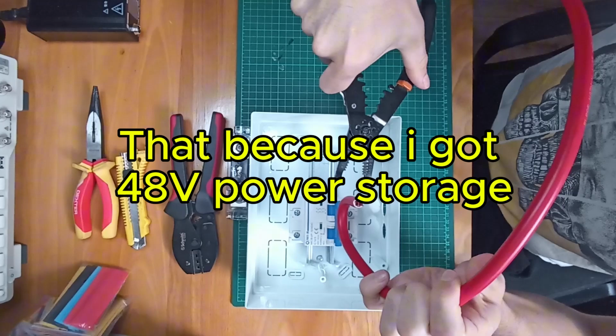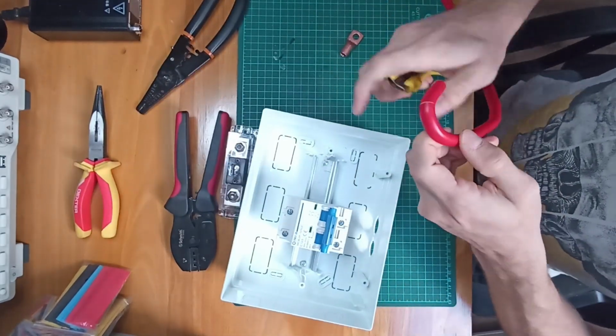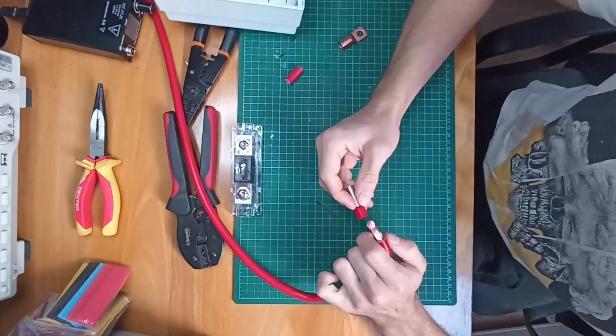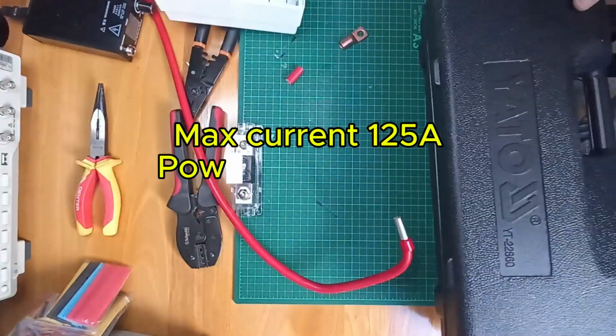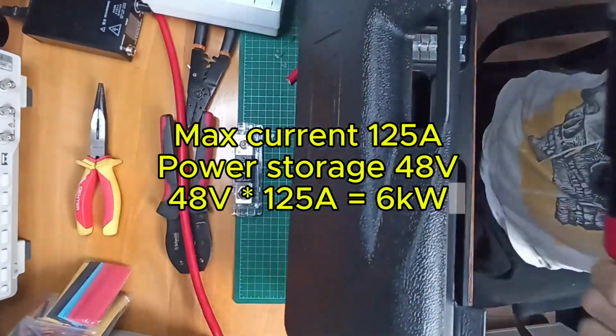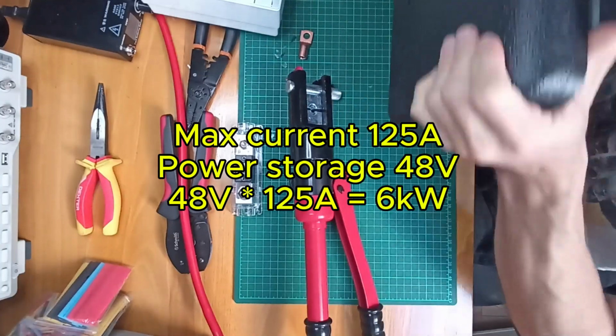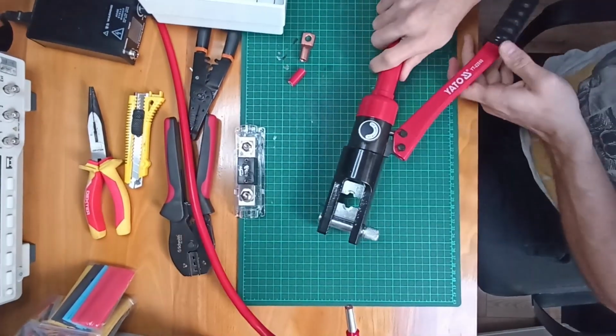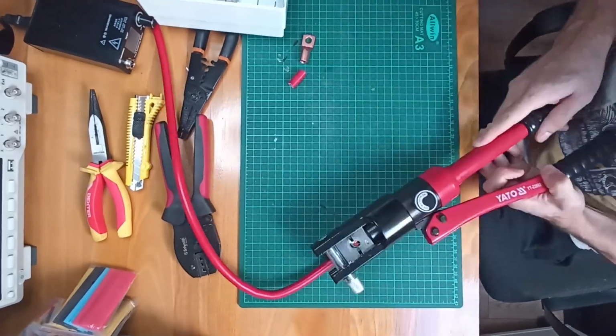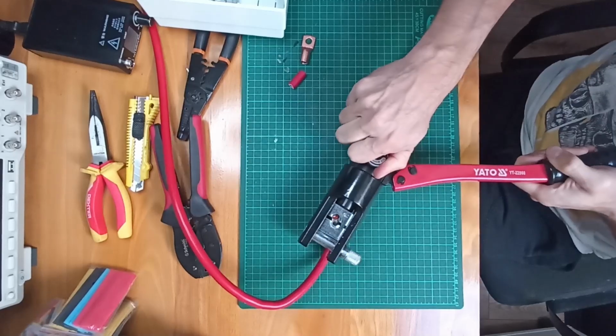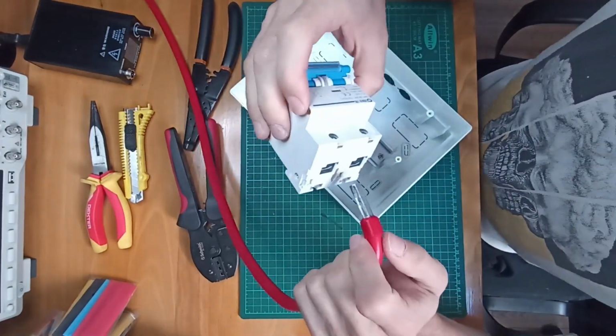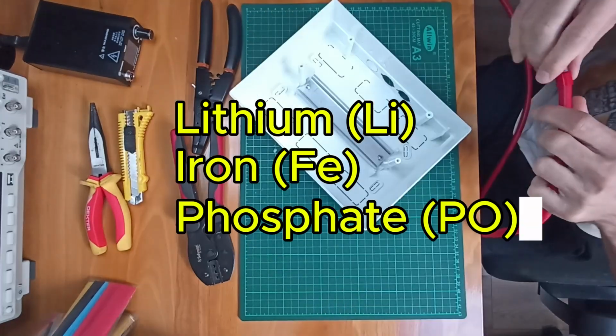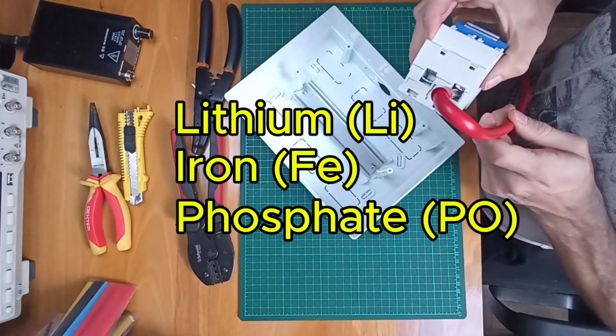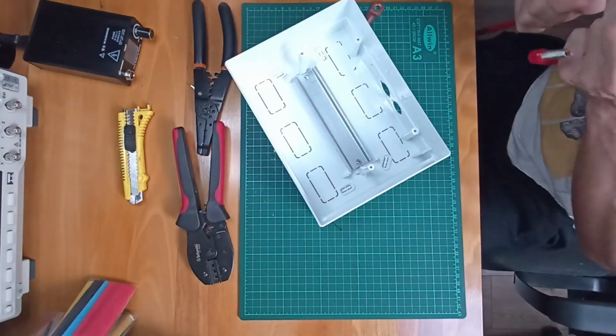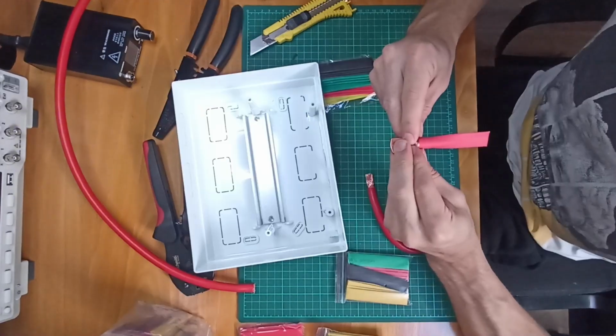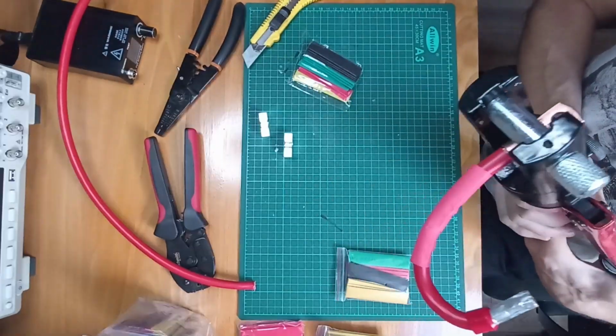That's because I have a 48 volts power storage. When it is charged to maximum, it can even reach 57 volts. That means 48 times 125 gives me 6 kilowatts, which is the max power that my inverter can handle. 57 times 125 gives me a little bit above 7 kilowatts, but that's not the problem. The main purpose of this breaker is to stop the tremendous current transfer that the lithium iron phosphate cells I will use can produce. Every single cell can handle up to 200 amps of continuous load, and in a moment of short circuit, it can produce whopping several thousand amps.